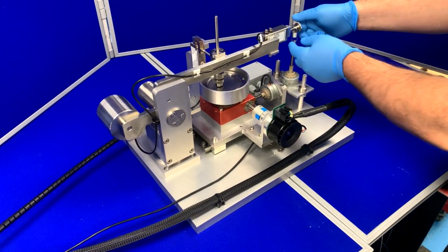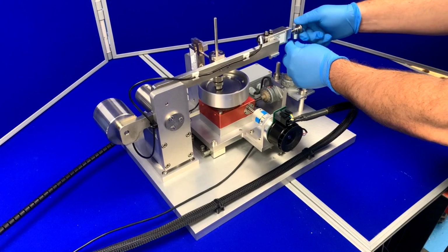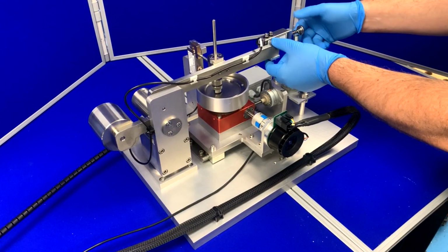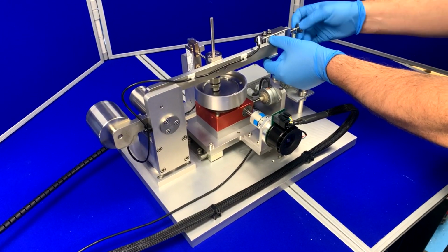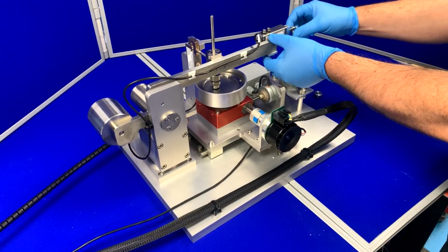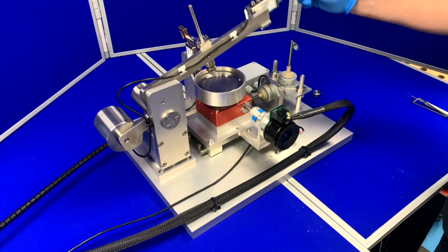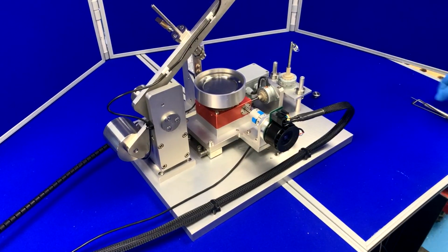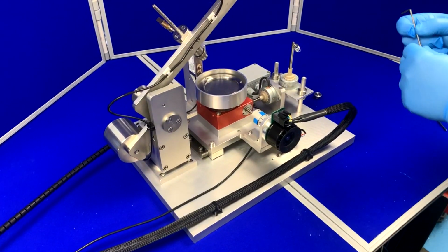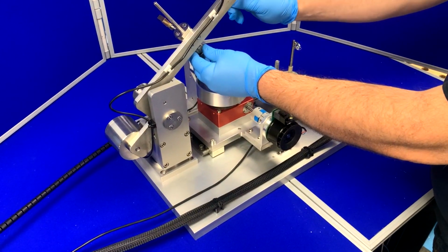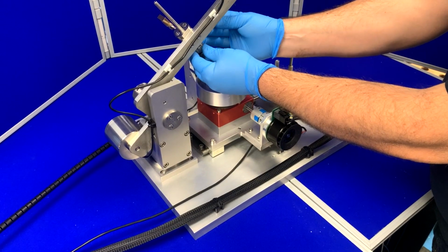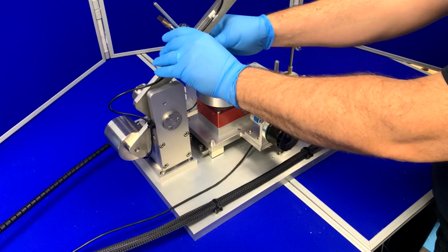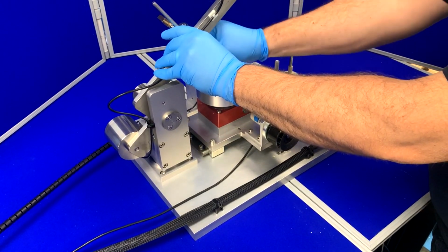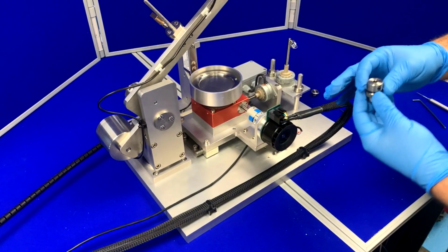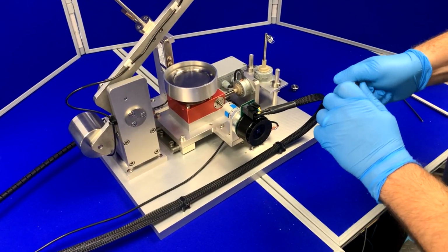To remove the specimens, unscrew the load knob on the load cell and slide off the spring. Lift the load arm, unscrew the grub screw securing the pin holder to the arm and remove the holder from the arm. Unscrew and remove the chuck. Using the specimen extraction tool, push out the specimen from the holder.